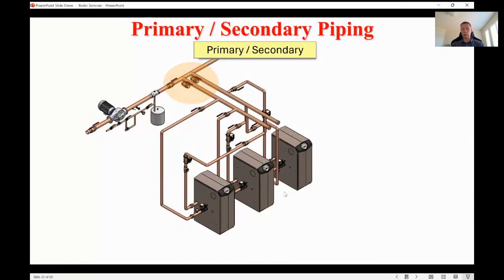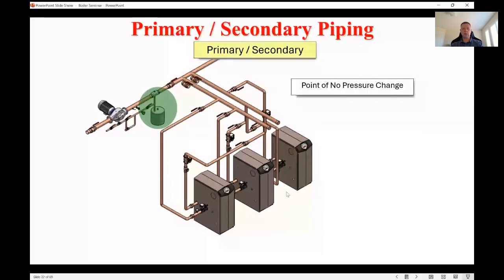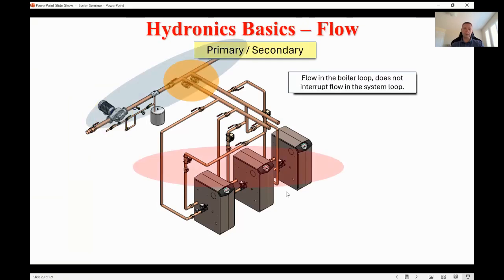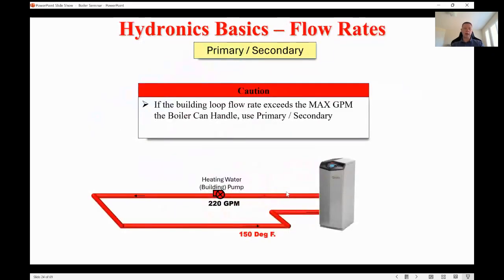With these low mass boilers, they have that static or very small flow range. You want to make sure the boiler's getting what it needs. Of course, you have the expansion tank. That's your point of no pressure change. So everybody knows that's the point in the system where that pressure will never ever change. And books have been written about it. You always want to pump away from that point of no pressure change there. So that's basically primary, secondary piping review in a nutshell. And it's very important with low mass boilers.